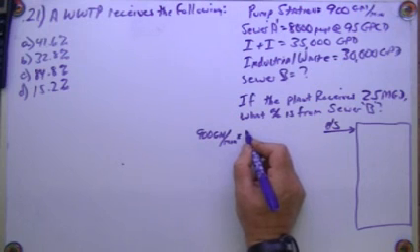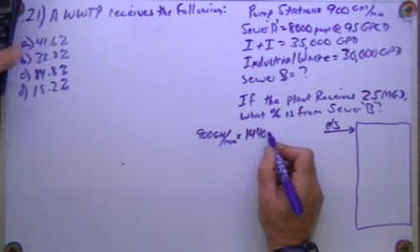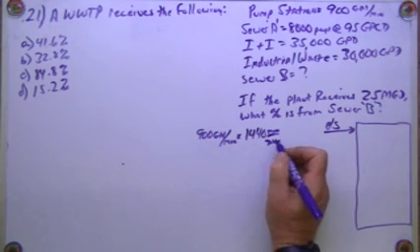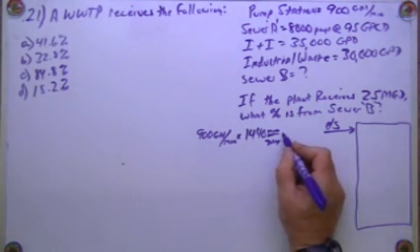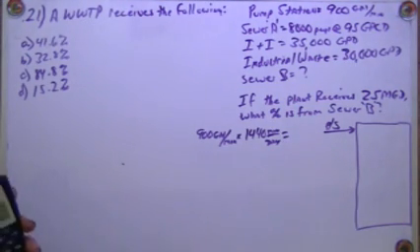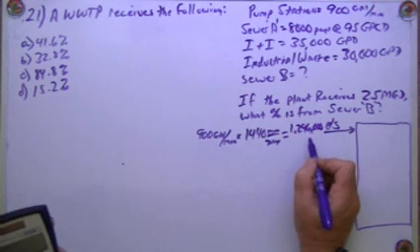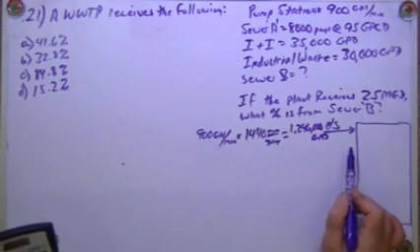Which is going to be 1440 minutes per day. And that's going to equal times 900, that's going to equal 1,296,000 gallons per day from the pump station.